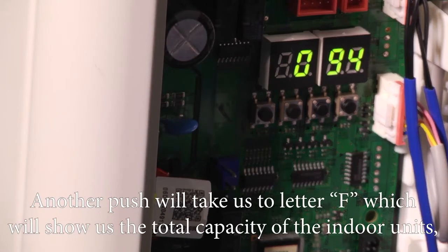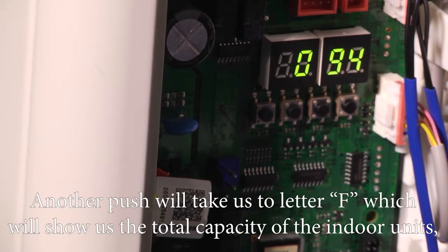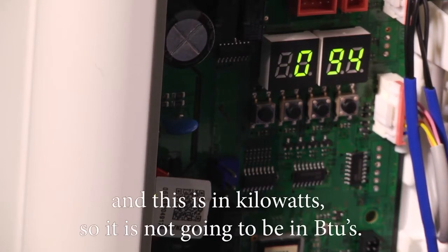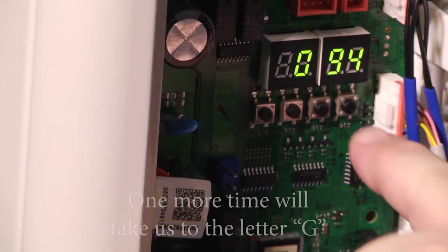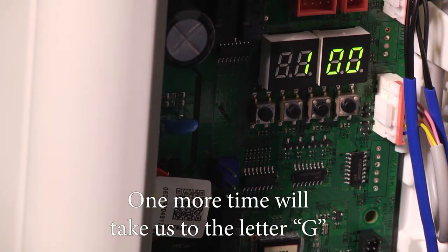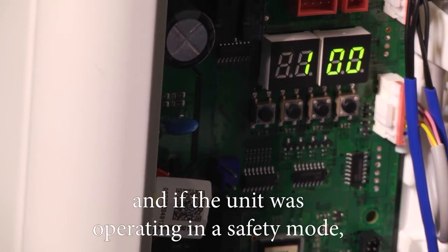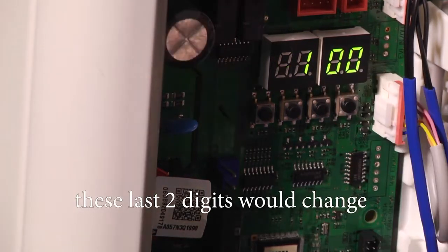Another push will take us to letter F, which will show us the total capacity of the indoor units, and this is in kilowatts, so it's not going to be in BTUs. And then one more time will take us to the letter G. If the unit was operating in a safety mode, these last two digits would change to let you know what safety mode you're operating in.